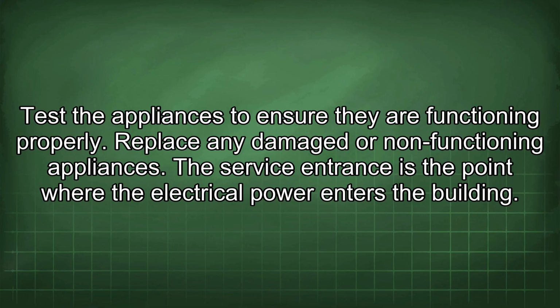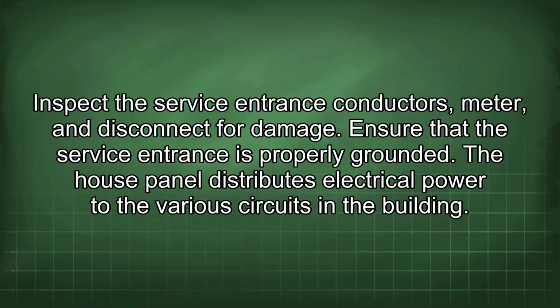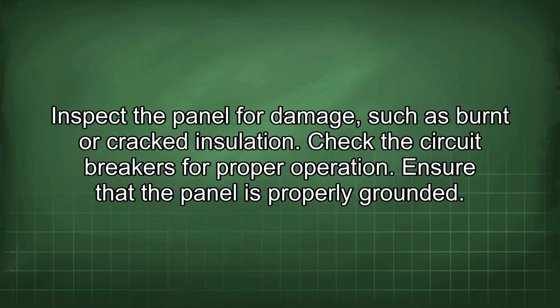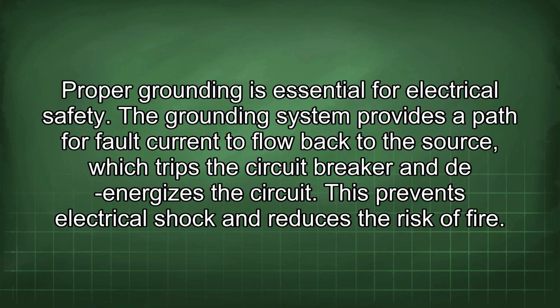The service entrance is the point where the electrical power enters the building. Inspect the service entrance conductors, meter, and disconnect for damage. Ensure that the service entrance is properly grounded. The house panel distributes electrical power to the various circuits in the building. Inspect the panel for damage such as burnt or cracked insulation. Check the circuit breakers for proper operation. Ensure that the panel is properly grounded. Proper grounding is essential for electrical safety.